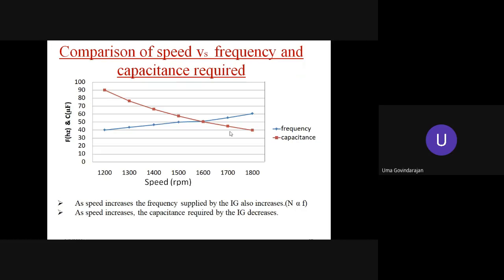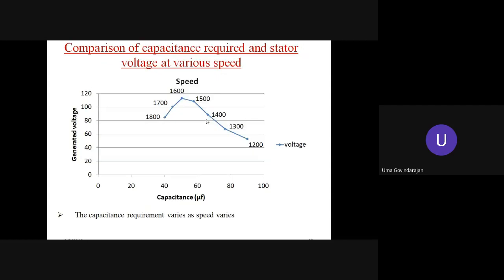Since it is a variable speed machine, or it is not connected to the grid, I am considering this speed range. As the speed of the machine varies, the requirement for the capacitance decreases, whereas the frequency of the machine increases. It is obvious for known reasons. And if we plot the variation of the generated voltage versus capacitance, as the speed varies, the requirement of the capacitance varies from between 40 microfarad to approximately 90 microfarad, for the speed variations from 1200 to 1800.